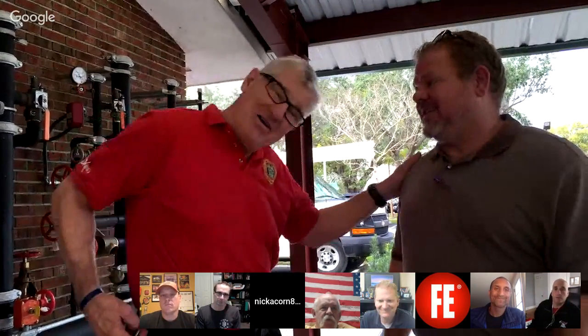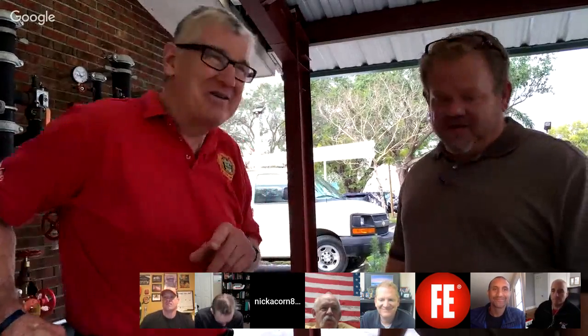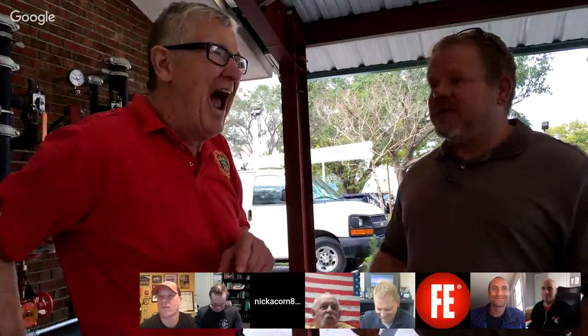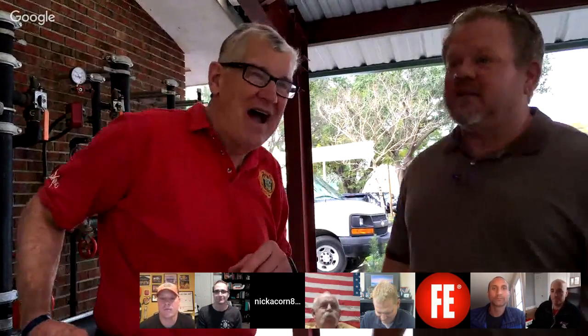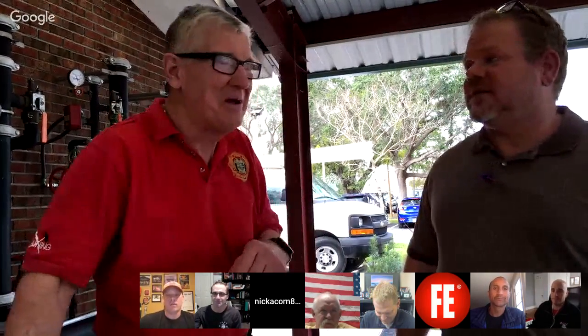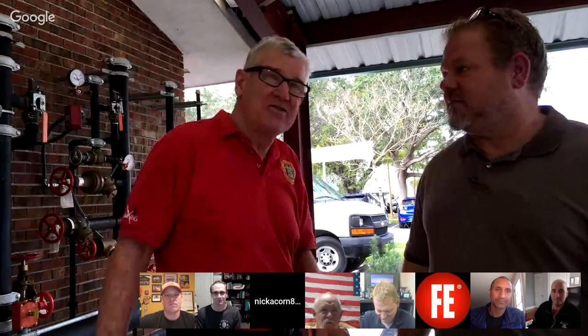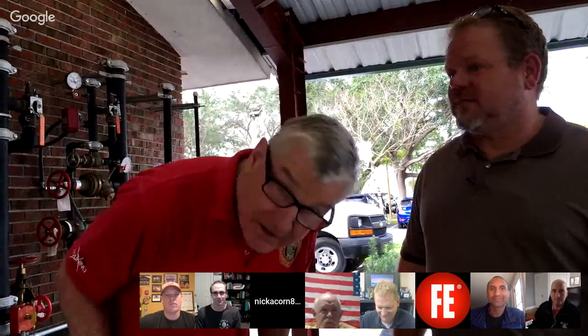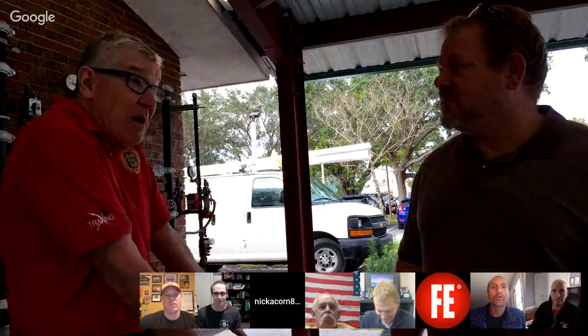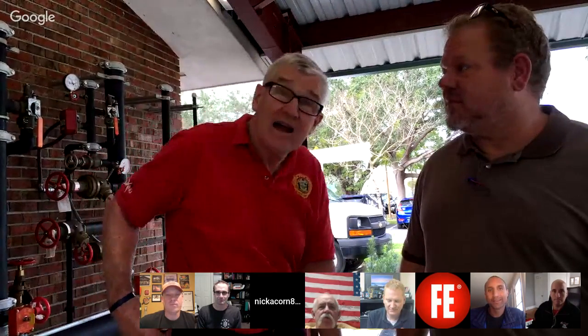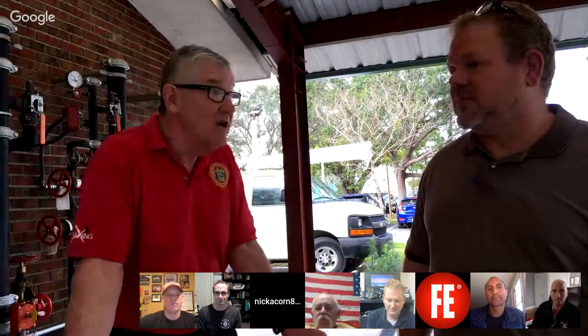Well, Mr. Collier, you're in the minority because I understand the liability. I asked a guy in a 55-story building, the suppression contractor, well, okay, we're going to pump this thing to 375 PSI. What? He says, you'll burst the system. Well, why is there a fire department connection? He says, well, failure of the fire pump is highly unlikely. Highly unlikely? You're on the Atlantic Ocean and the fire pump is 20 feet from sea level. What do you mean highly unlikely?